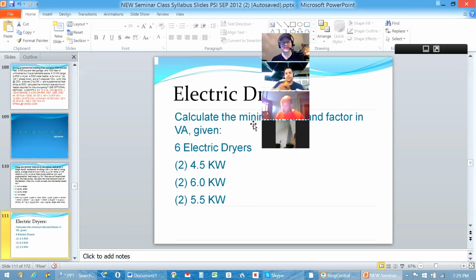And there have been a couple of questions, guys, out there about dryers in a laundromat area. If it's a laundromat in a residential apartment complex, that would apply under this table. But if it's a quick wash or a coin-operated deal down on Main Street, that's going to be 100% of those values. There's no table derating for dryers that are not residential in nature. So you're looking at a pretty simplified table, the minimum value being 5,000 no matter what. On the table on the left-hand side of page 71, put 5,000 watt minimum real big across the top of it so you don't forget. And it comes out of the article at the bottom of the preceding page, like we looked at earlier.